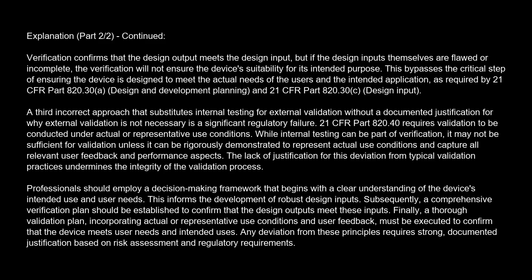This bypasses the critical step of ensuring the device is designed to meet the actual needs of the users and the intended application, as required by 21 CFR Part 820.30A, Design and Development Planning, and 21 CFR Part 820.30C, Design Input.